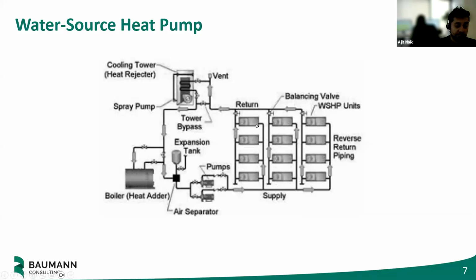They're really beneficial because you can exchange energy. If half of your units are calling for cooling, half of your units are calling for heating, you've got a balanced load, and this system can actually be used to share the heat among different units. In the middle of the winter, though, when it's real cold outside, all of these guys are going to be drawing heat out of that common water loop. So we need a boiler or some kind of heat addition to provide that heat at the low end. Historically, this has been a gas boiler, but it doesn't have to be, and we're coming to that. Same thing in the summer when all of these units are in cooling, the water is going to start getting hotter and hotter as these units reject heat to it. So we need a cooling tower, blow some air off of it, cool that water back down and get it to within the range that the heat pumps can use it.